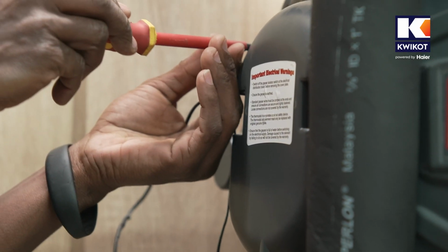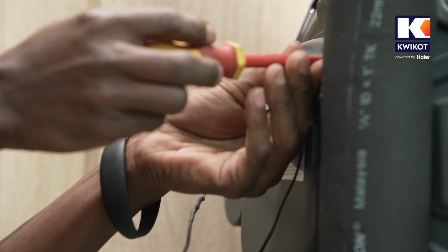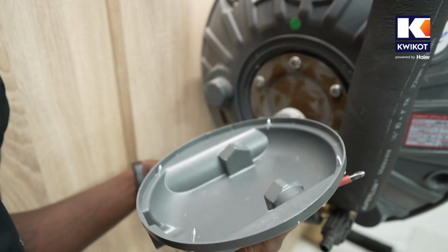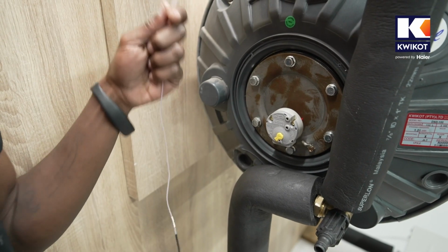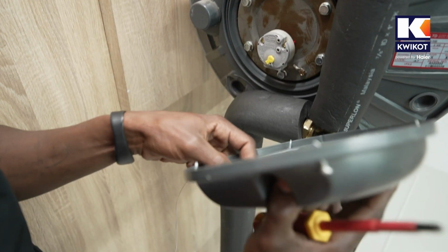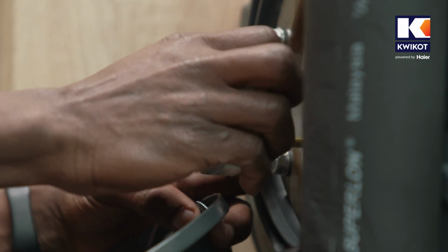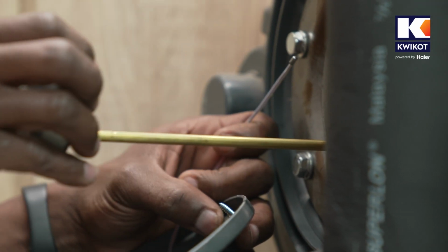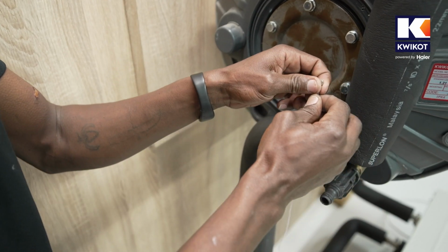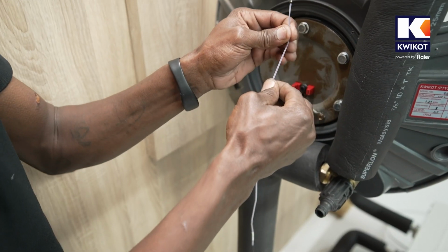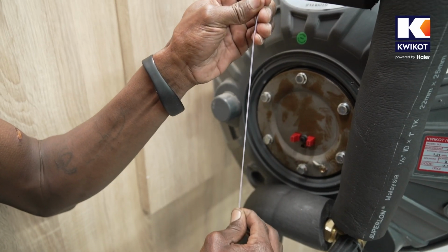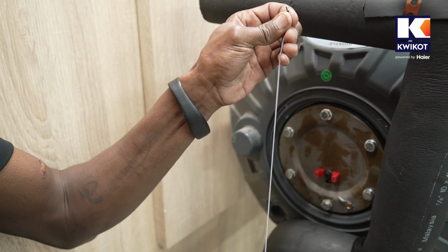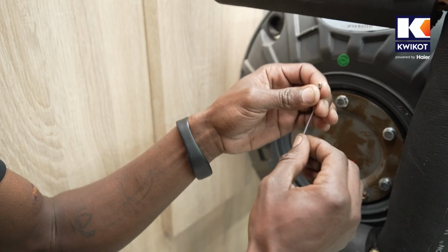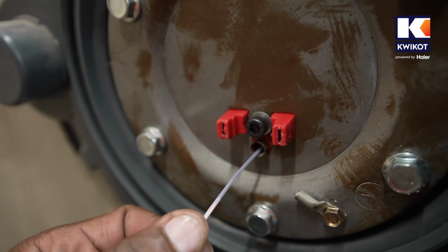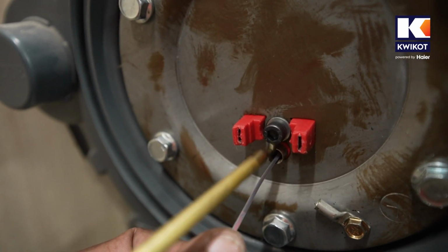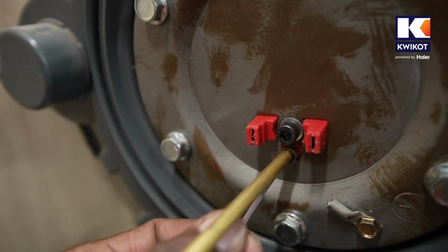Now up at the water heater we will remove the cover on the element and the thermostat, and then we feed the sensor wire through this hole in the cover, and next we pull out the thermostat itself, and we're just going to press down the whole of the white section of the microsensor wire with your fingers so that it doesn't get stuck or damaged when it's inside the thermostat. And then we reinsert the thermostat into this lower socket and insert the microsensor along with it.